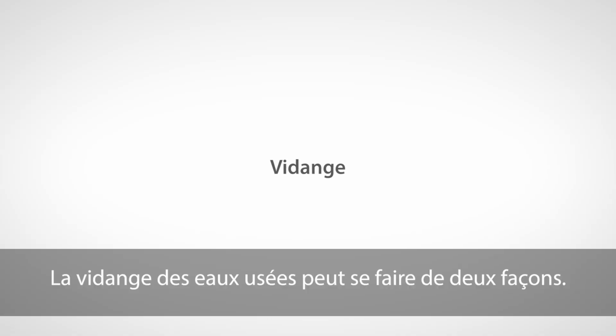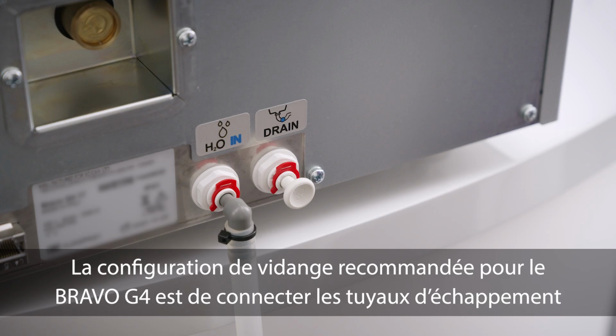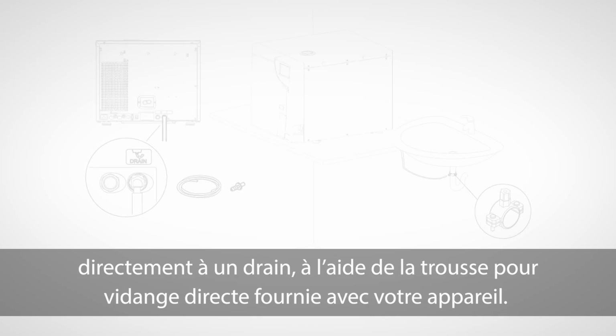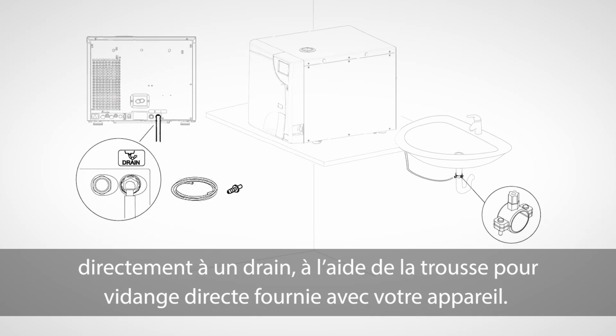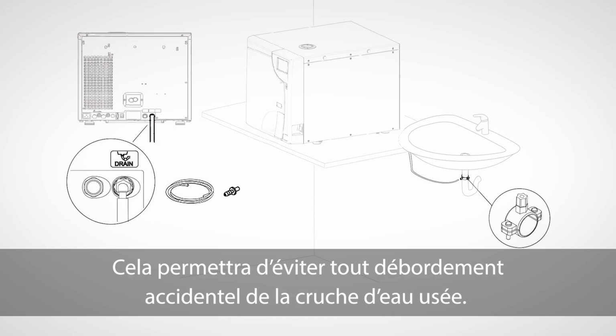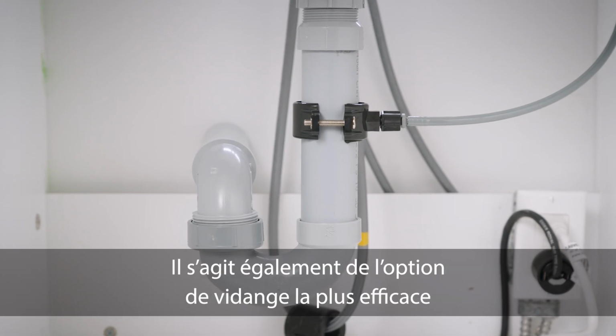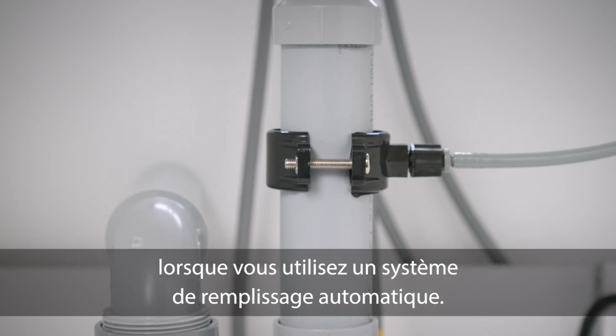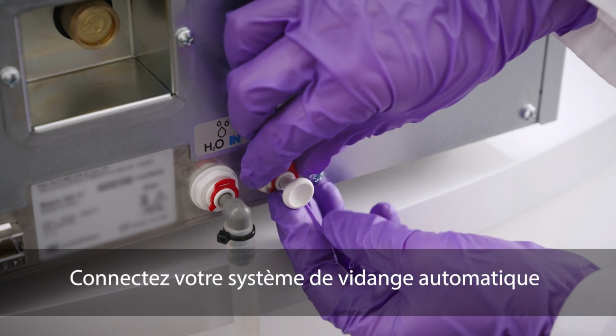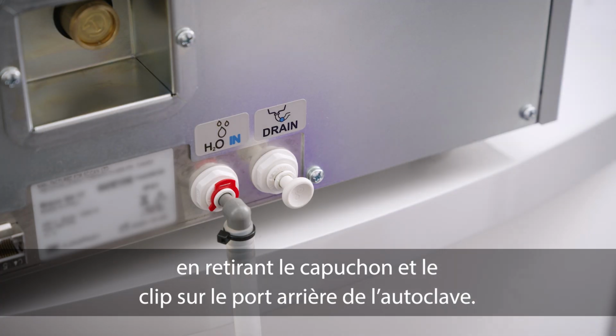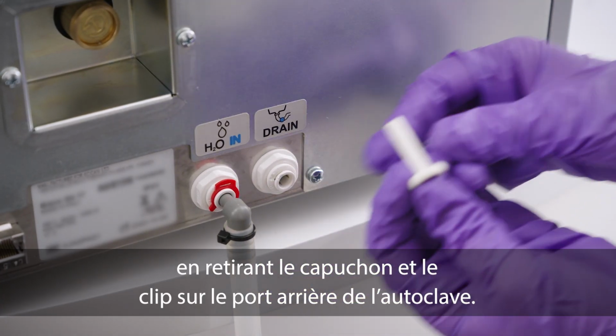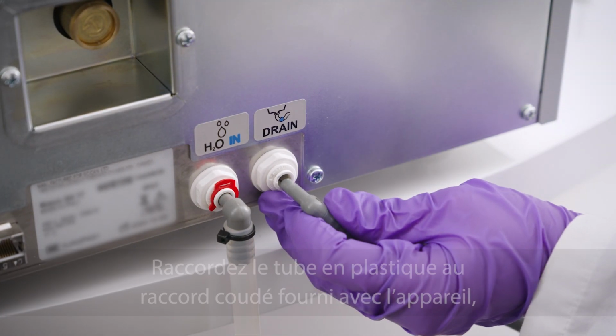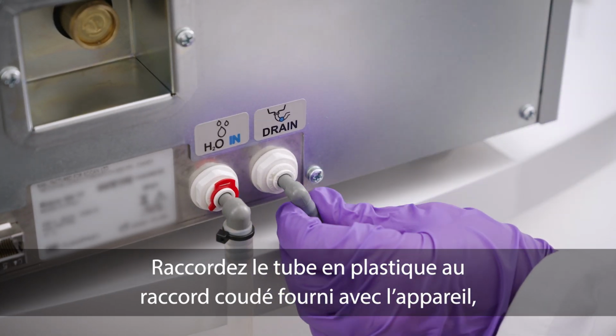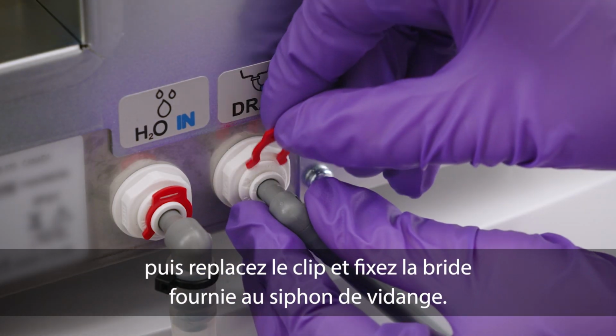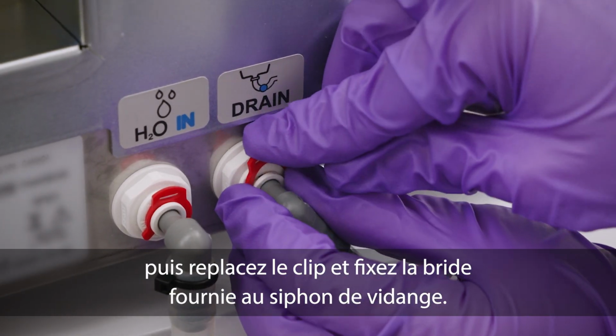Draining wastewater can be done in two ways. The recommended draining setup for the Bravo G4 is to connect the exhaust hose directly to a drain, using the direct-to-drain kit supplied with your unit. This will prevent accidental waste bottle overflow. This is also the best draining option for when you are using an automatic filling system. Connect your system to automatic drainage by removing the cap and clip on the rear port of the autoclave. Connect the plastic tube onto the elbow union supplied with the unit, then refit the clip and fasten the supplied clamp to the drain siphon.